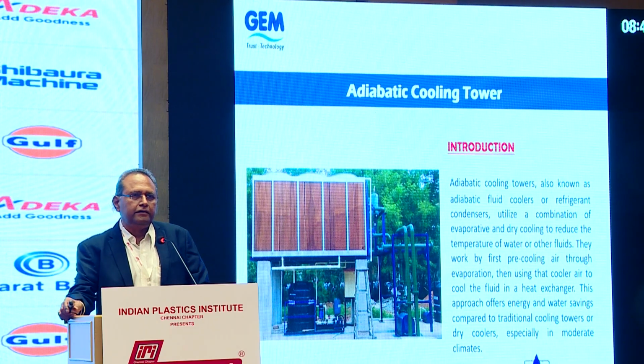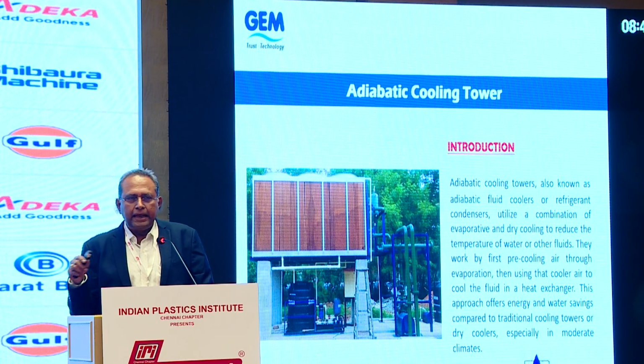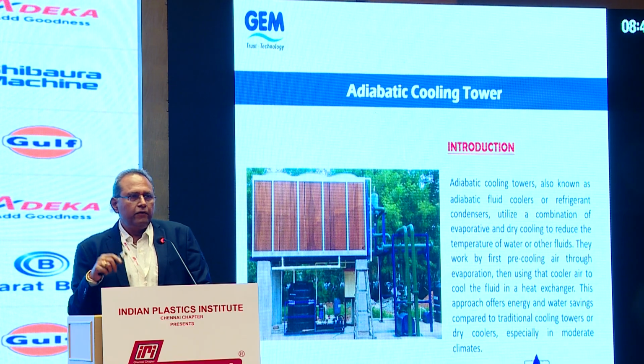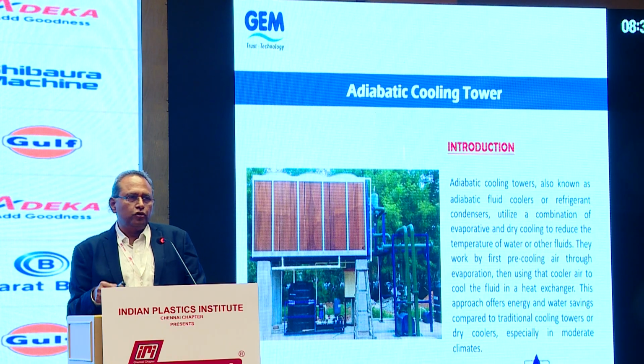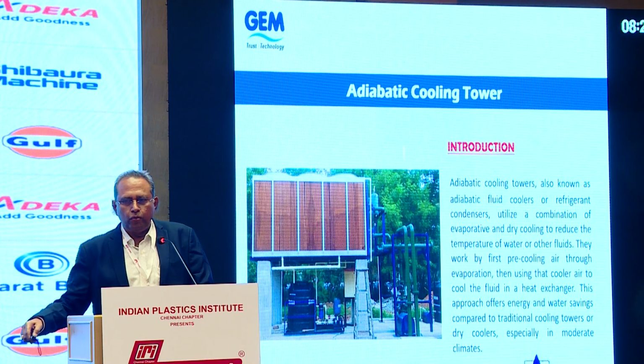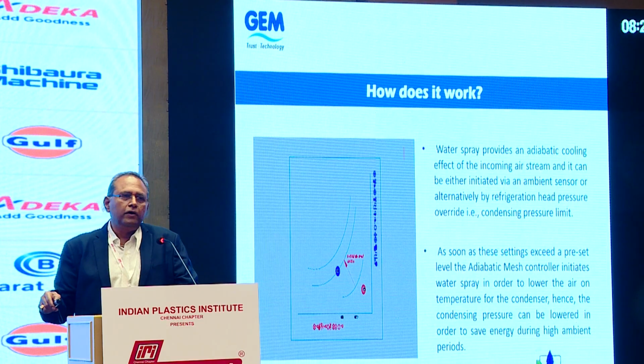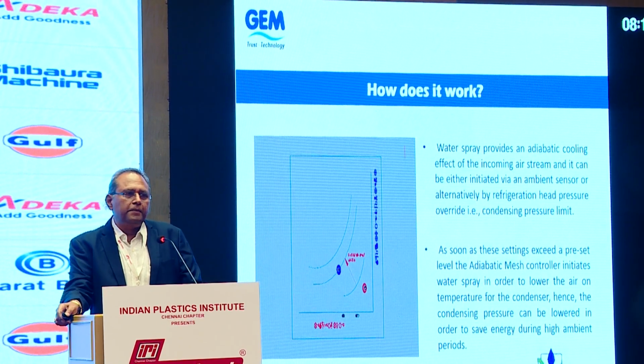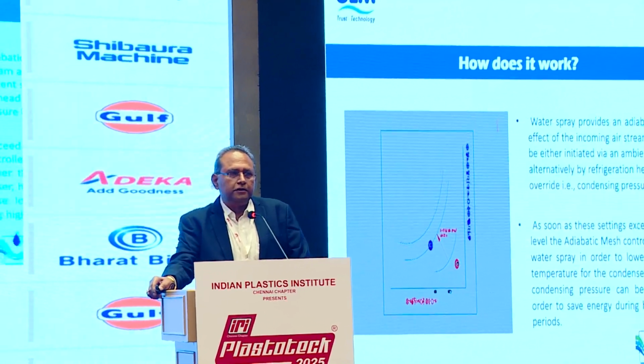Now, adiabatic cooling tower is a concept by which we add environmental pads or adiabatic pads before the radiator, so that the radiator can be selected suitably and the closed loop system can be maintained at wet bulb plus 3 to 4 degrees, similar to a cooling tower. So how it works is basically the ambient dry bulb temperature is what will determine the process temperature in a dry cooler. But once you reduce the inlet temperature to the radiator, then automatically you can achieve lower than ambient temperature. So this gives a typical arrangement of the dry cooler.